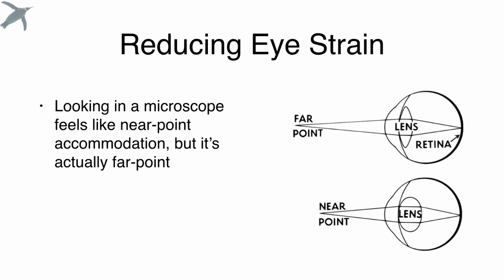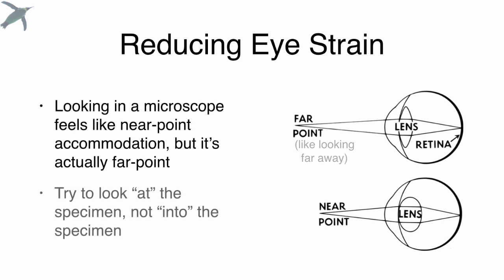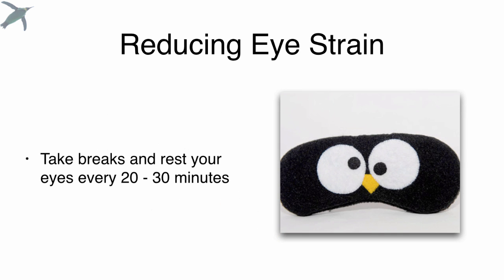Here's another thing: your focusing, your focal point. Your eyes automatically adjust as objects move toward and away from you, and we call this accommodation. Most people approach microscopy with a near-point accommodation. In other words, you focus your eyes as if you were reading. But actually, it's far-point accommodation. Try to look at the specimen and not into the specimen. And it sounds a little touchy-feely, but experiment with it. And you're going to find that you can help to reduce eye strain.